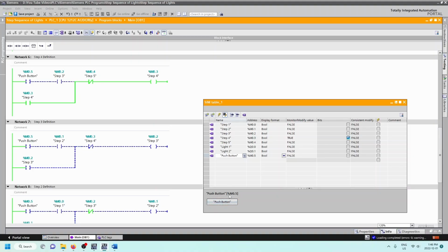So the reason for that is because remember on the timers and stuff, when you hit this push button, the scan cycle is happening so fast that I may be hitting this push button for like a millisecond or two, but in that millisecond or two, the program can go 1, 2, 3, 4, 5, right? Even though I put it in descending order here, 5, 4, 3, 2, 1 with my steps, every time I hit this push button, I'm actually sending a number of signals through on that push button, and so it's just flying through, and now I'm on step number 3, and I was on step number 4, right? So every time that I hit this push button, I just randomly go to a different step. Now I'm on step number 2.